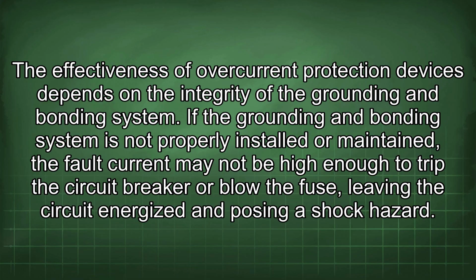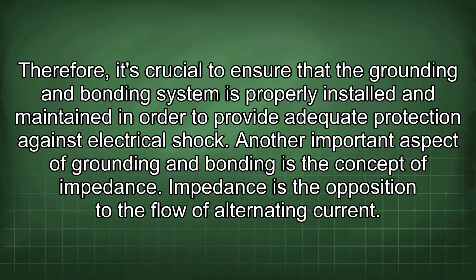If the grounding and bonding system is not properly installed or maintained, the fault current may not be high enough to trip the circuit breaker or blow the fuse, leaving the circuit energized and posing a shock hazard. Therefore, it's crucial to ensure that the grounding and bonding system is properly installed and maintained in order to provide adequate protection against electrical shock.